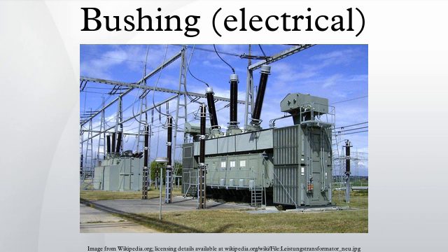Paper insulation. Another early form of insulation was paper. However, paper is hygroscopic and absorbs moisture, which is detrimental, and is disadvantaged by inflexible linear designs. Cast resin technology has dominated insulated products since the 1960s, due to its flexibility of shape and its higher dielectric strength. Typically, paper insulation is later impregnated either with oil, or more commonly today with resin.